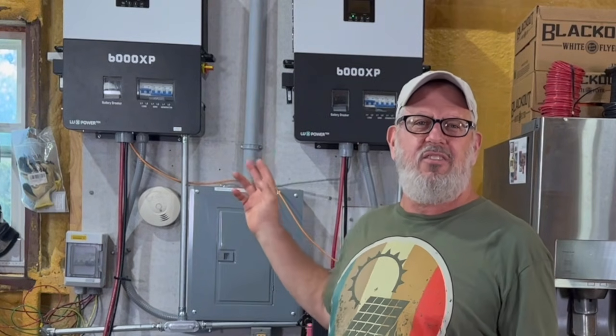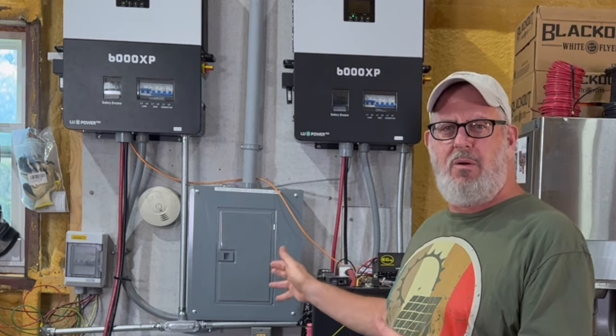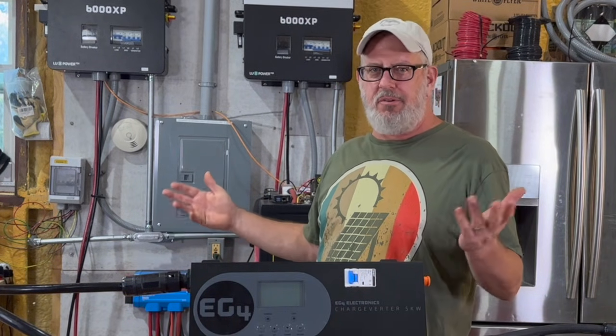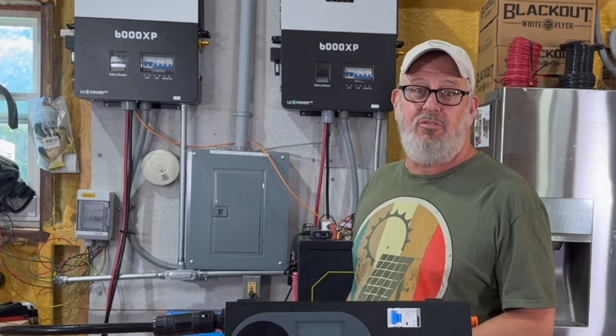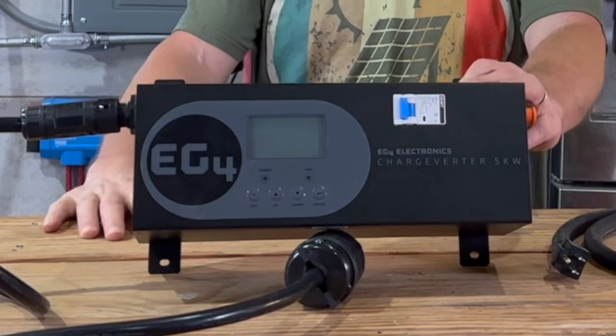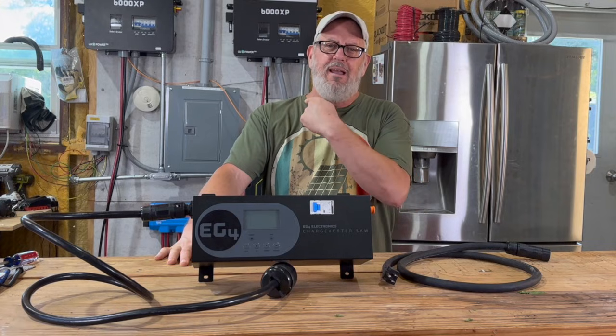This is important, because my 6,000 XP inverters can technically accept 240-volt power, but it has to be really clean power — like what you'd get from the utility company on the grid. Most small generators don't put out power that clean, and if you hook them up directly to your inverter, you could do some serious damage. Signature Solar even says the number one cause of inverter failures is people connecting them to a dirty generator. The ChargeVerter fixes that problem by conditioning the power it sends straight to your batteries.